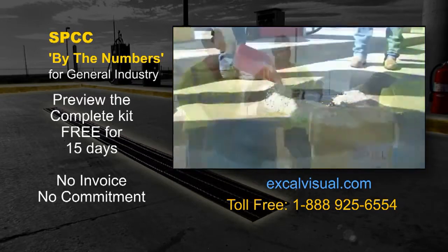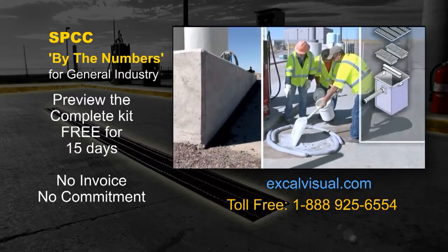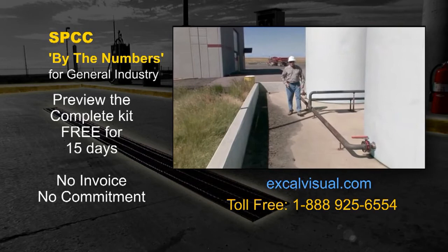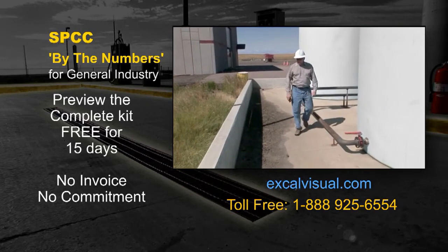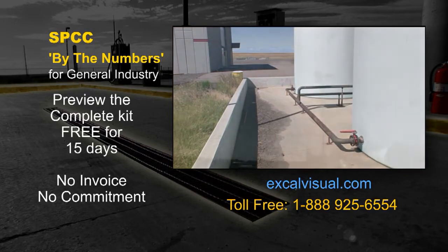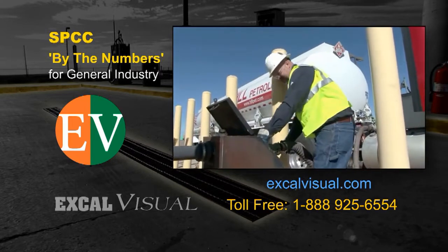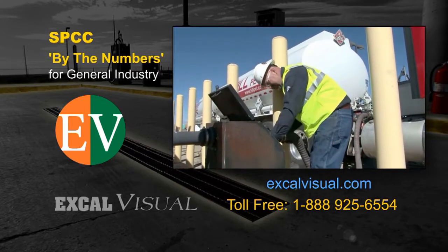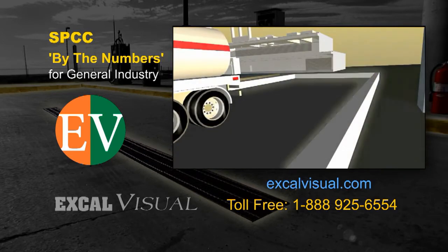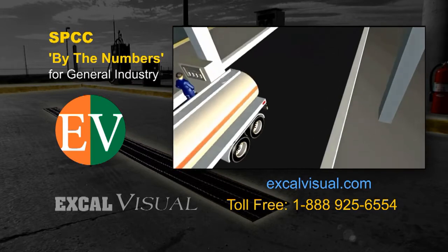While quick response teams are acceptable, passive methods of containment like berms and catchments are preferred because they do not require any active human intervention and will work 24/7, even when the facility is unoccupied. In addition to storage areas, SPCC plans must also address oil transfer operations. Transfer operations also require protection. Some type of secondary containment or diversion is often used.